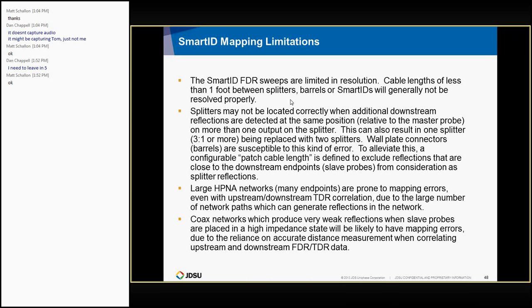What that would look like in your reflection pattern would be a 20-foot reflection at one point, and another 20 feet beyond that you'd see another reflection. So you would expect the splitter to be at the last point, the first point where you might see a difference, or where the probes are attached. But in fact, those are just barrels. And it's because the run to the previous splitter is identical in length that they're susceptible to being combined into a single splitter. So that's why the patch cable length is a little bit of a kludge to cover that.